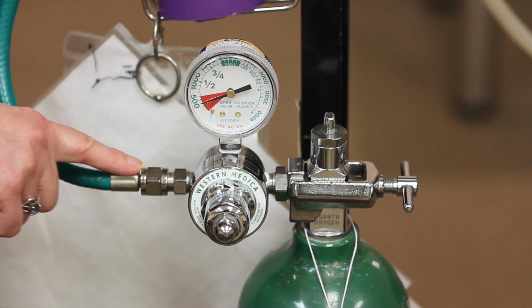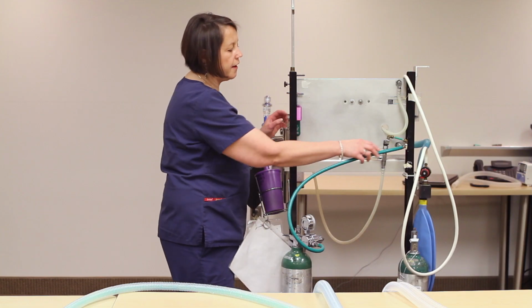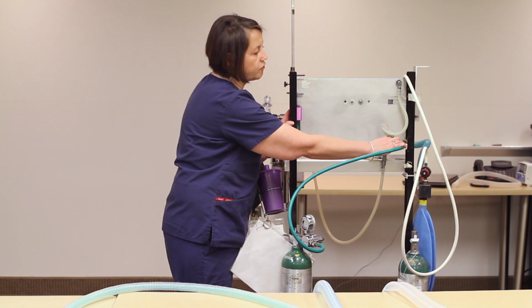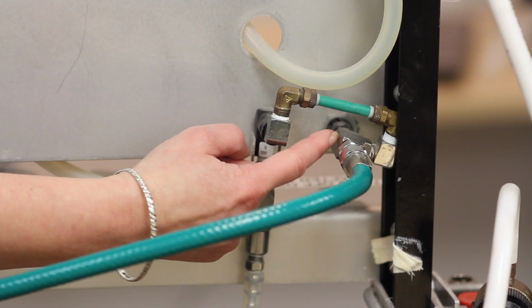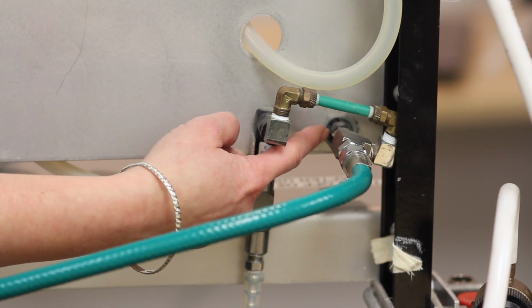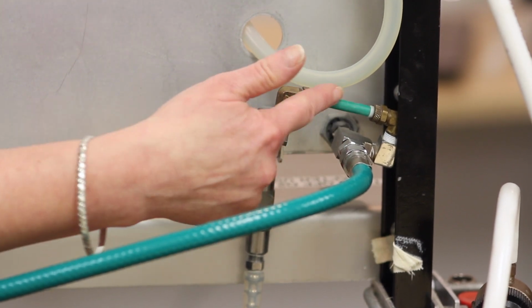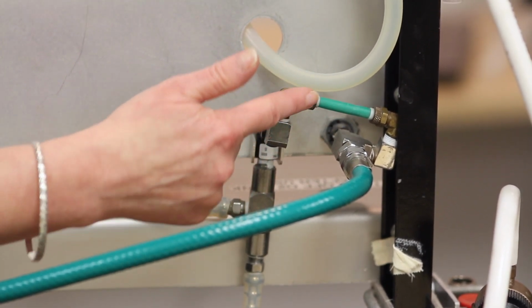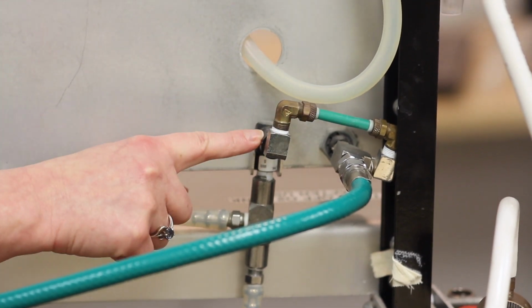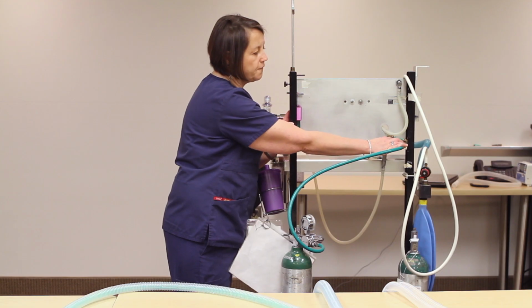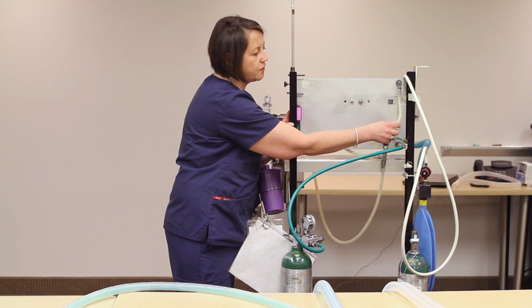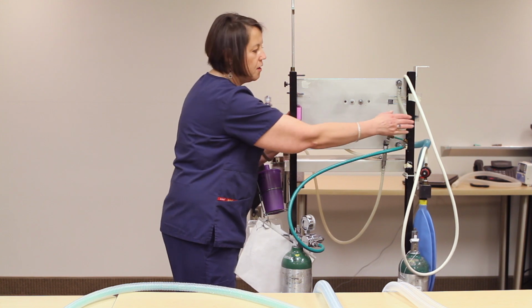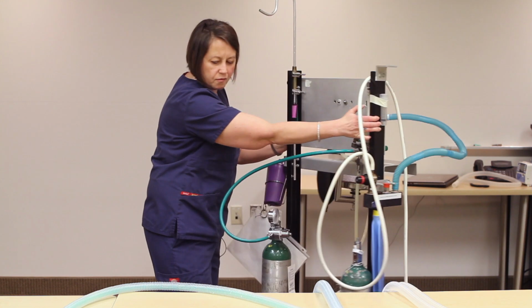Once the oxygen leaves the tank, it goes through this green line, which is attached to the flow meter on the other side. This location is where it goes into the flow meter, and this part also ties in your oxygen flush valve on the other side. When I flip the machine around, this is the tube coming out of the back of the flow meter. So we'll go ahead and flip that machine around.